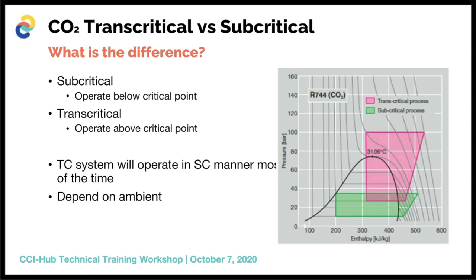The confusion sometimes is that a transcritical plant operates only in a transcritical manner, but that is actually not so. In most areas the ambient temperatures are fairly cold, and you would find that even a plant called a transcritical plant will operate in a subcritical manner because of the ambient conditions.